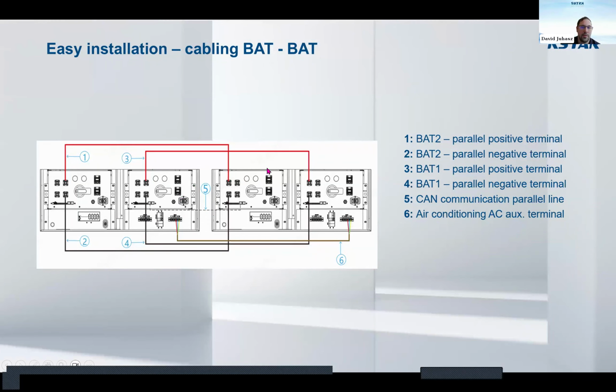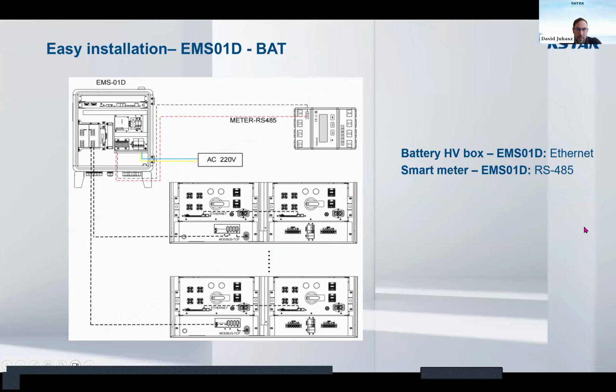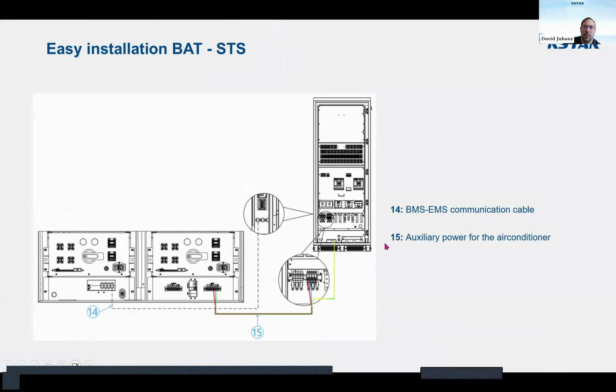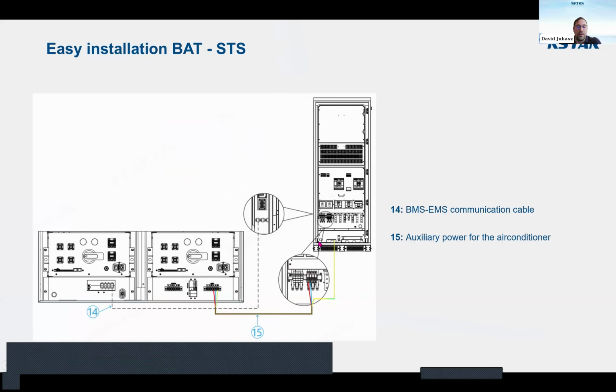It is 2 cabinets, high voltage box connected to each other with the prefabricated battery cables, the CAN communication, and the air conditioner also in parallel. This is how we connect the system to the EMS01D by RS485 and the meter also. The meter is for RS485 and the EMS01D needs to be connected via Ethernet. Okay, the BMS and EMS communication is also connected by Ethernet to the STS and between the STS and the battery, and also the auxiliary power for the air conditioner.